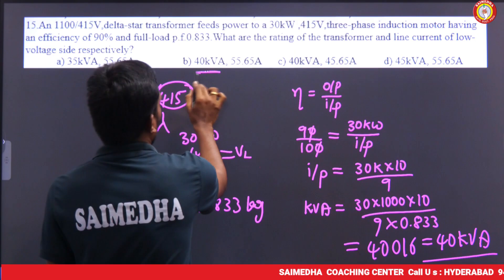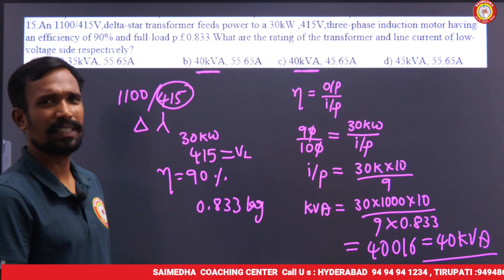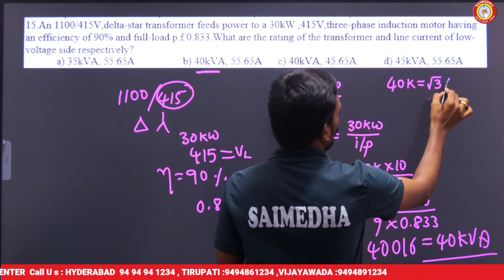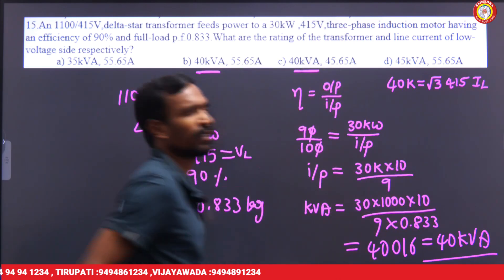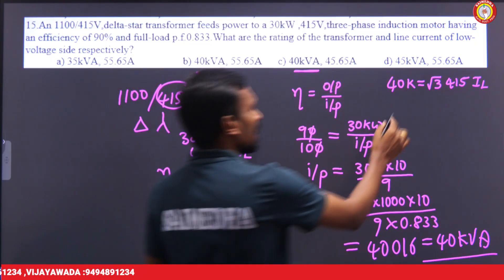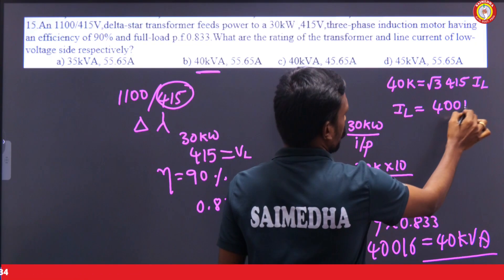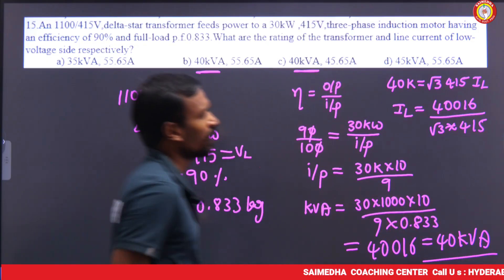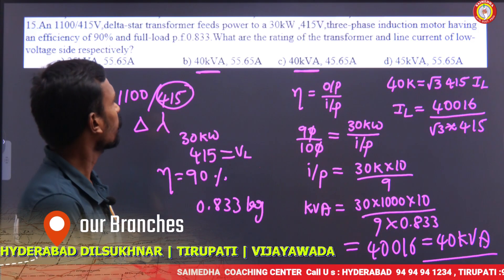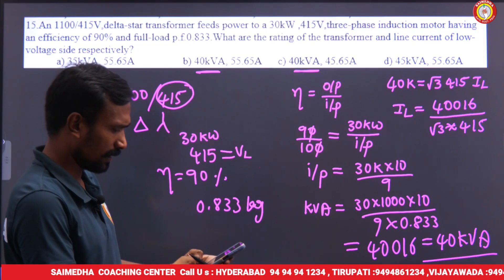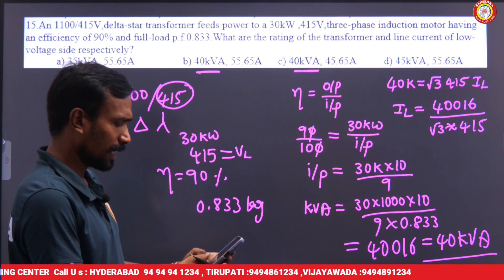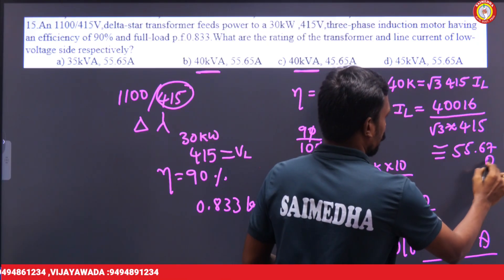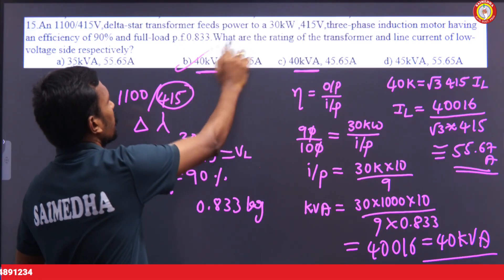40 KVA equals root 3 times VL times IL. VL is 415 volts. So IL equals 40,016 divided by root 3 into 415. Can you tell me — 45 or 55? Let's calculate: 40,016 divided by root 3 into 415 gives approximately 55.67 amperes.